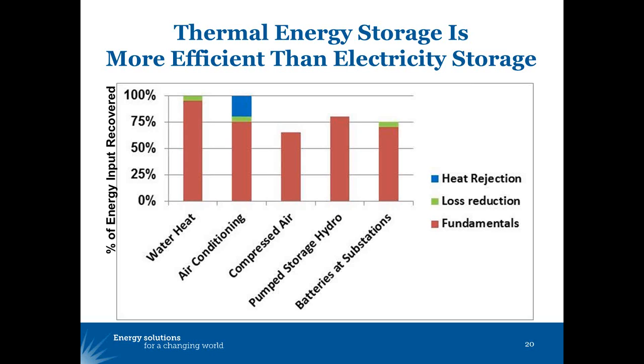Keep in mind that at peak hours, the average line losses on utility systems are about 9% around the country, but that's about 6% off-peak and 15% on-peak. The marginal line losses - the ones that would be saved by reducing peak load - the marginal on-peak line losses are about 1.5 times the average on-peak line losses. So you can wind up avoiding 20% line losses by reducing circuit loading during afternoon hot summer peak hours.